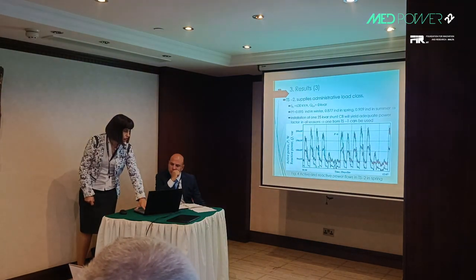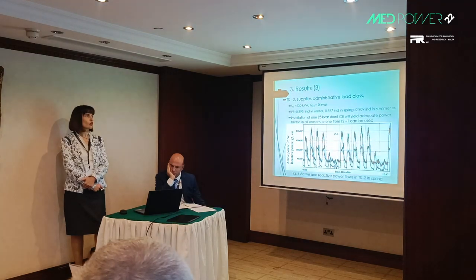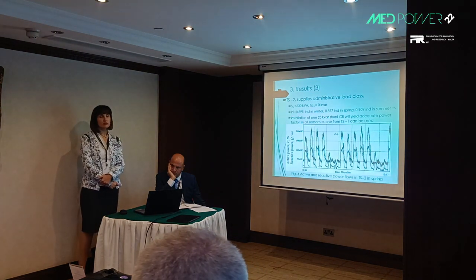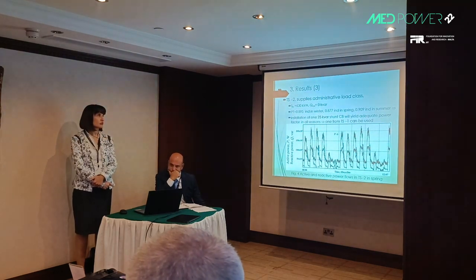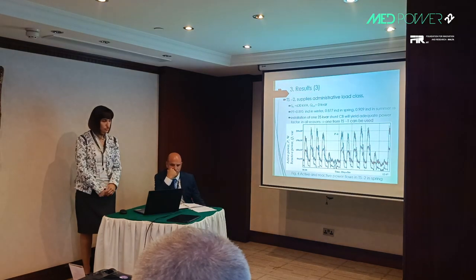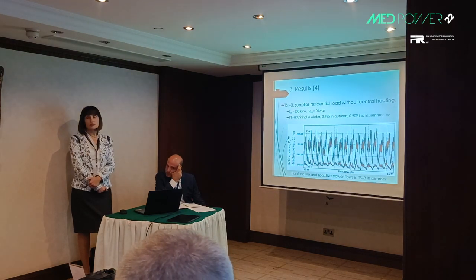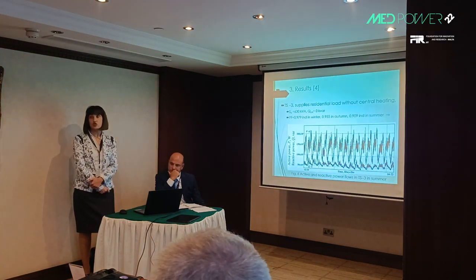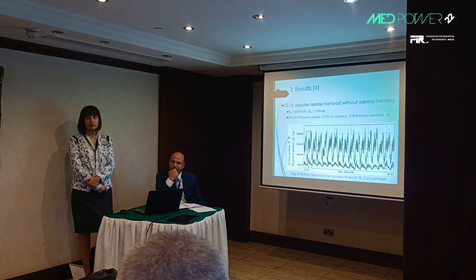In transformer substation 2, the power factor is pretty low — below 0.95 in all seasons. It is found that installation of only one capacitor bank with a rated power of 25 kvar will improve the power factor to the desired range. In transformer substation 3, it is found that in the summer season the power factor is below the wanted range, and installation of one or two capacitor banks of rated power 25 kvar will improve it.